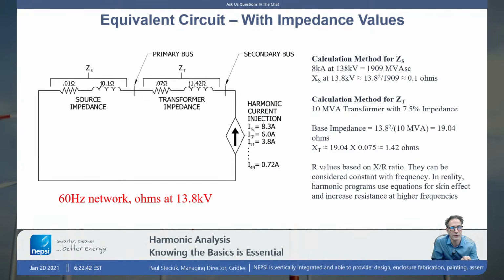Okay, I'm going to calculate the source impedance based upon an 8 kA, 138 kV short circuit, and I get a value of 0.1 ohms. You've got to remember that the source impedance, we've got to reflect it through the transformer if we're doing the analysis at 13.8, and that's actually what I'm doing. So I reflect that impedance through the transformer. So X of S at 13.8 is 0.1 ohms.